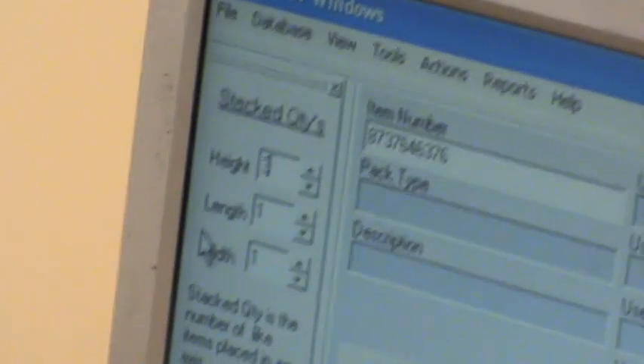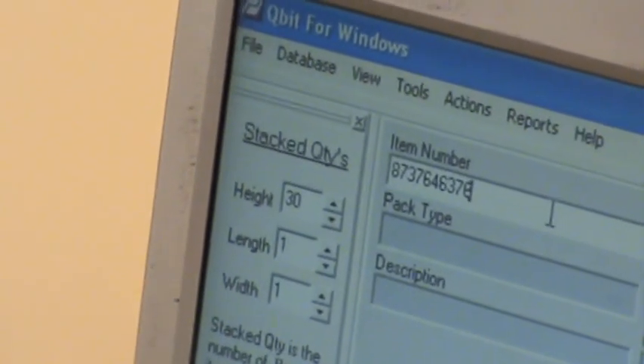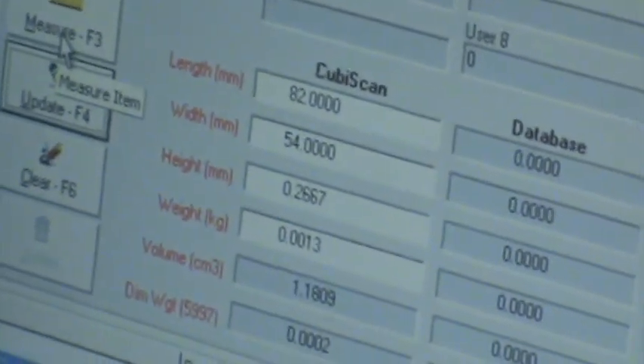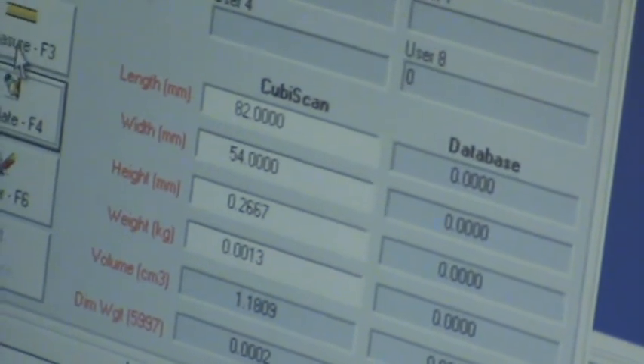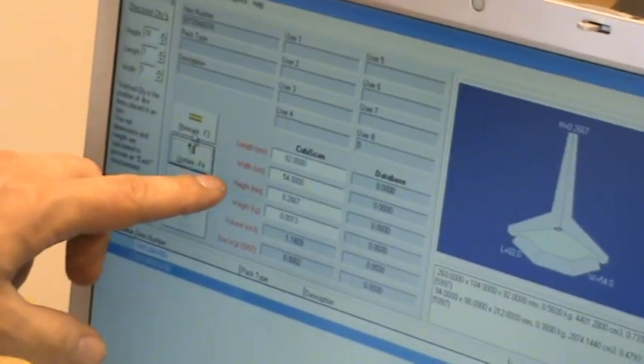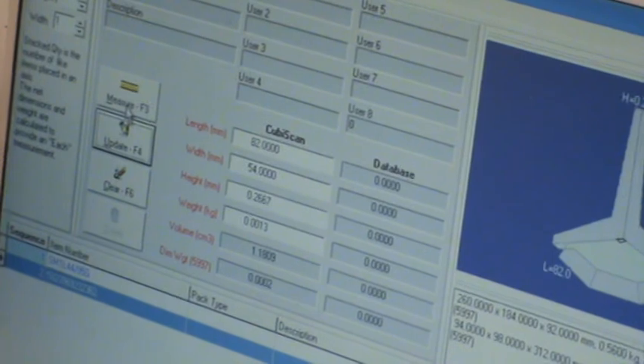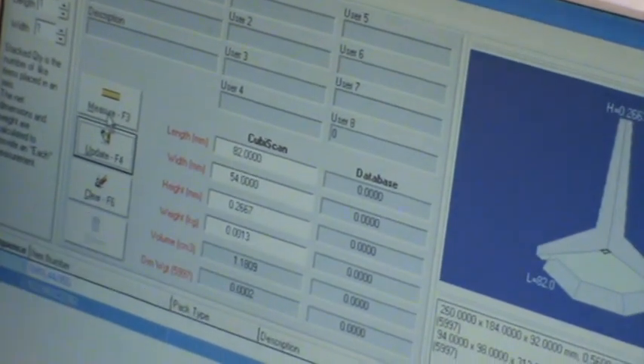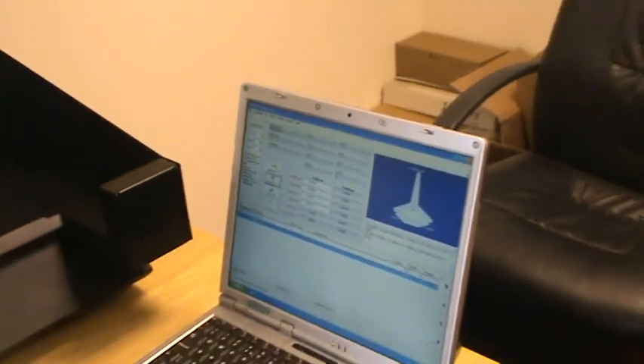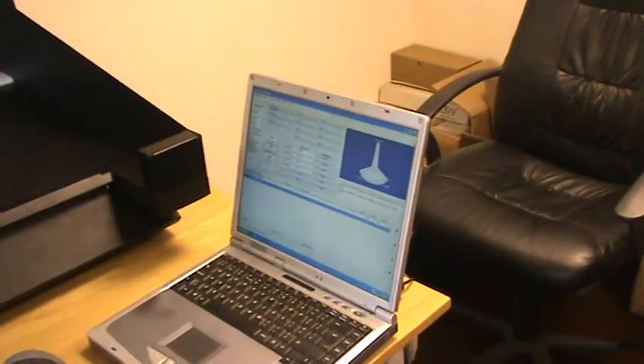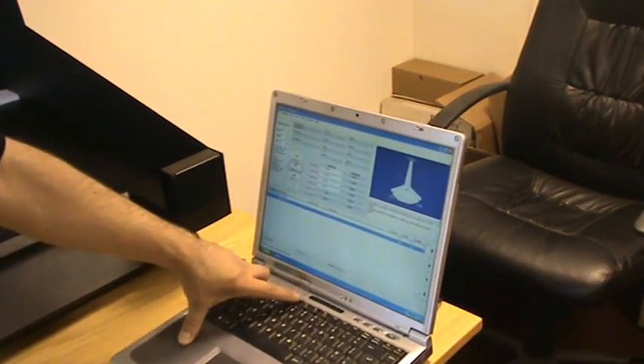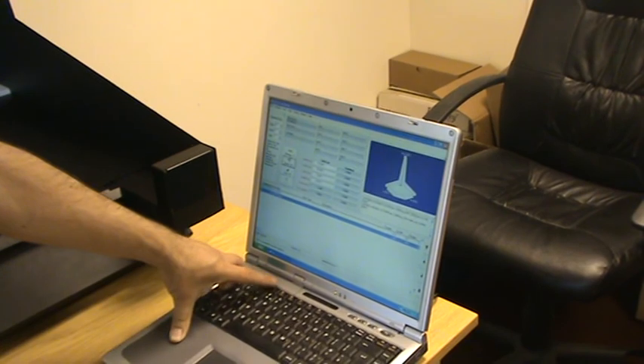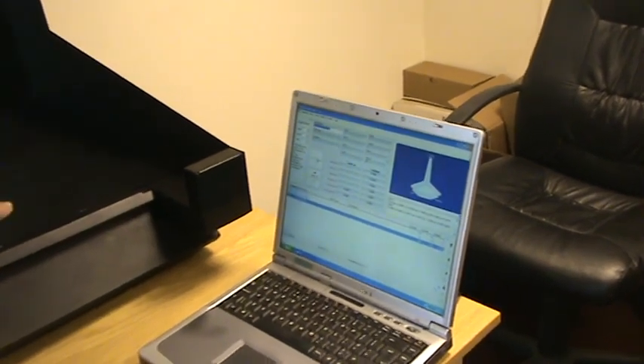Over here in the stacked quantity on the software, we just put in that it's 30 high, and again ask it to measure. What it does now is take the height and the weight and divide it by the number we put in, which is 30, giving us an average for the one. The length and width stay the same, it's just the height and weight which have been divided by 30. It's given us a height of 0.2667 of a millimeter and about 1.3 grams, which is well under the tolerance of the machine, giving you an average for just the one, which in some cases is a lot more accurate than measuring just a single unit.